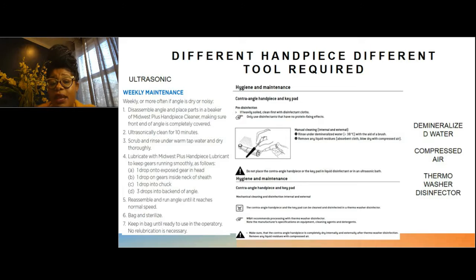The second excerpt is asking that the handpiece be rinsed with demineralized water. So not just tap water; it's saying that you need demineralized water for that IFU. In order to completely dry this handpiece, compressed air is asked to be utilized. Compressed air is not something that's normally found inside of your sterilization area. So again, before you actually place an order for a particular handpiece or a dental device, you've got to read that IFU. Ask your reps for that IFU and read it thoroughly so that you will have the equipment that you need in order to reprocess it. This particular handpiece also requests a thermal washer disinfector.